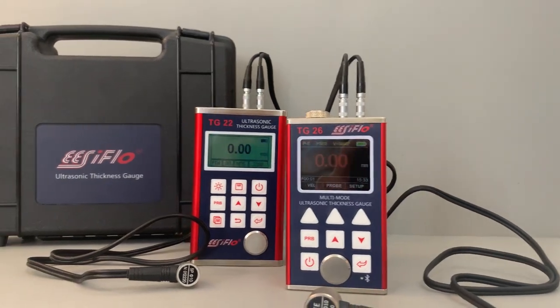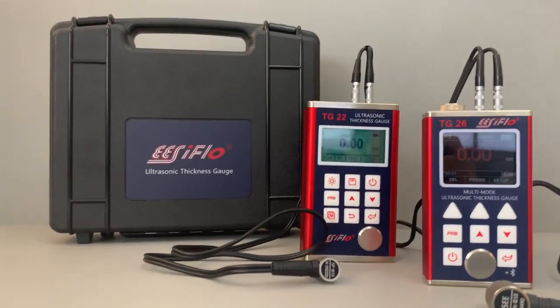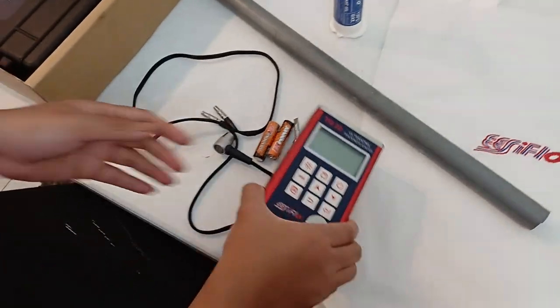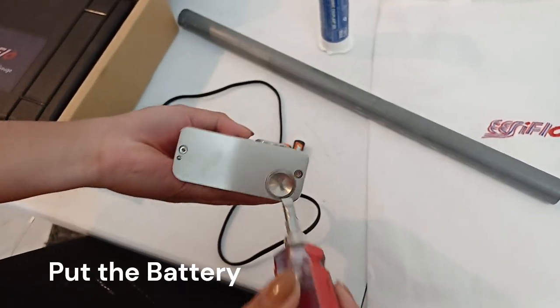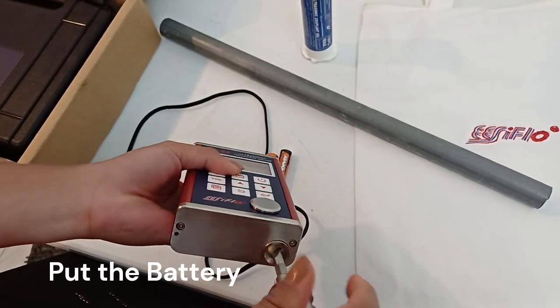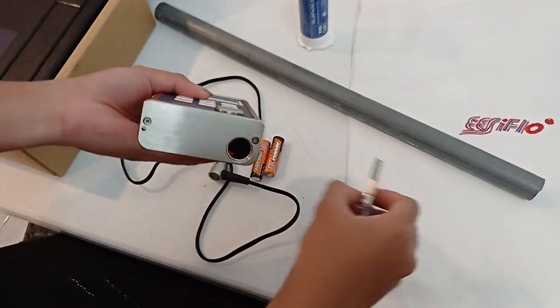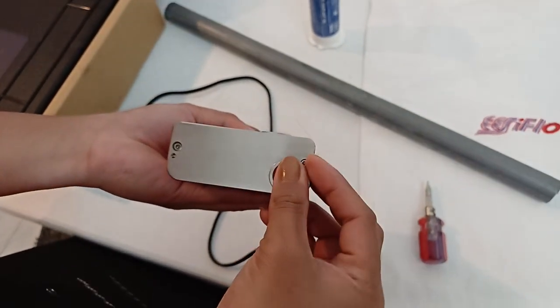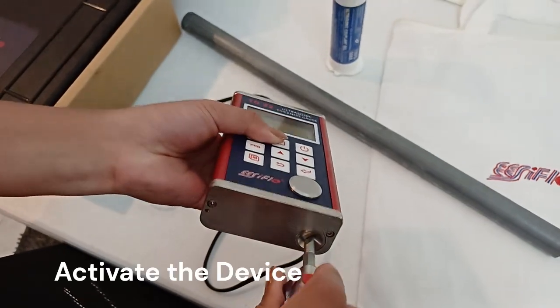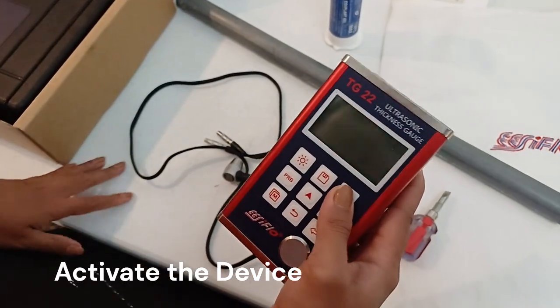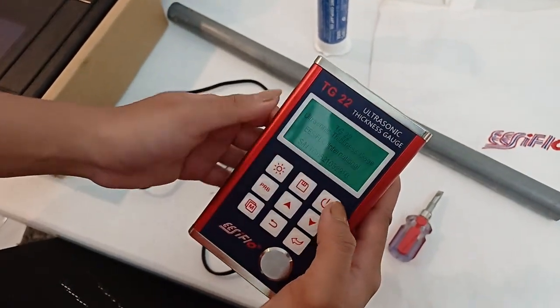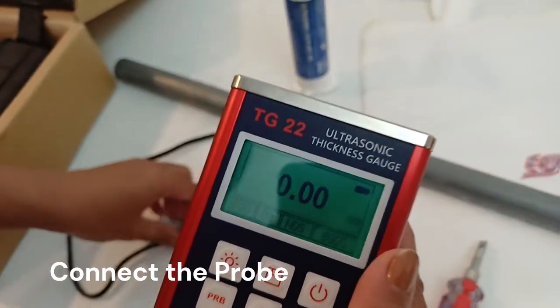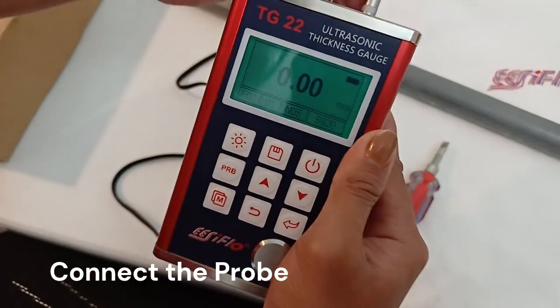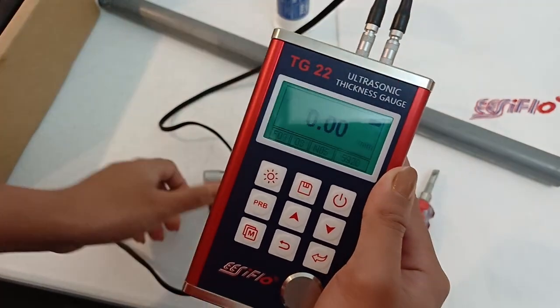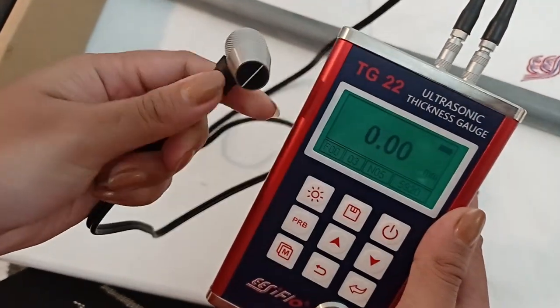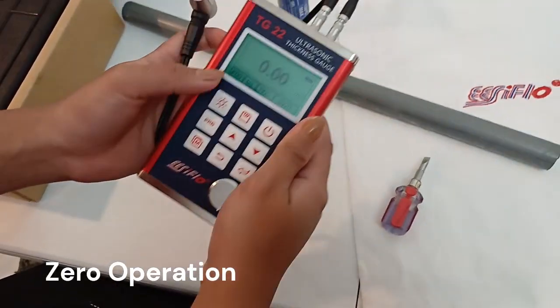In this video, we will show you how the ultrasonic thickness gauge TG22 works. To start the instrument, put the battery in first. And then press the button until the display activates. Then connect the probe to the device. Next, set the work mode and ensure the correct probe model is selected. Perform the probe zero operation.